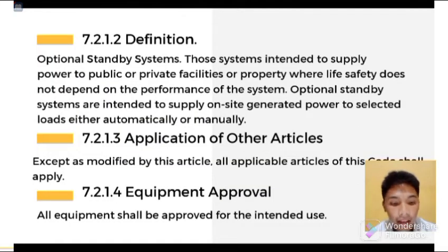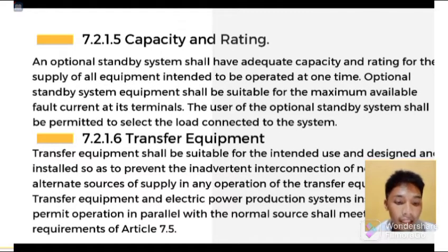Capacity rating. Adequate capacity. The optional standby system shall have adequate capacity and rating for the supply of all equipment intended to be operated at one time. Optional standby system equipment shall be suitable for the maximum available fault current at its terminals. The user of the optional standby system shall be permitted to select the load connected to the system. Transfer equipment. Transfer equipment shall be suitable for the intended use and designed and installed so as to prevent the inadvertent interconnection of normal and alternate sources of supply in any operation of the transfer equipment.